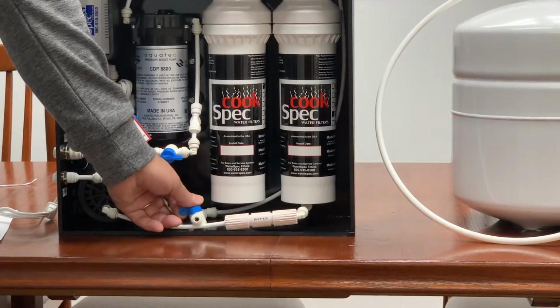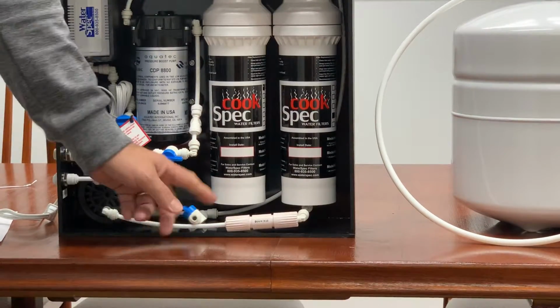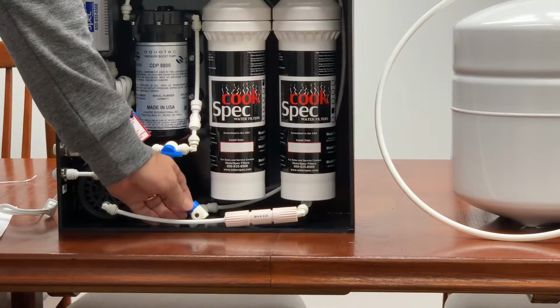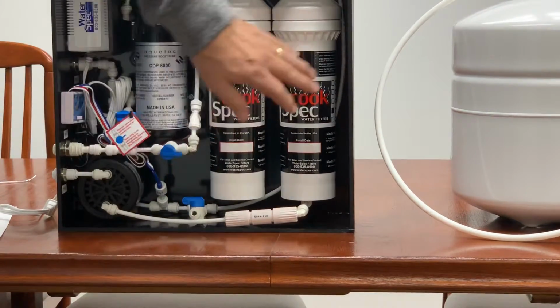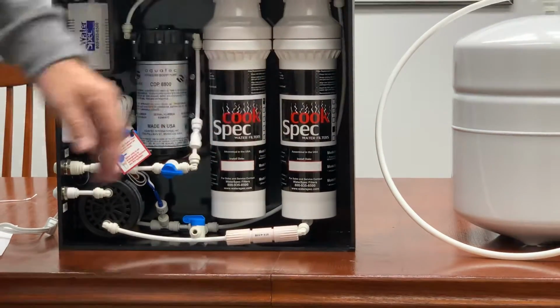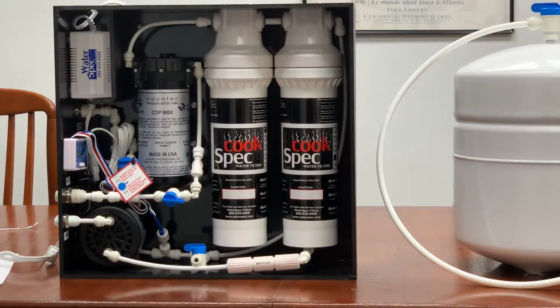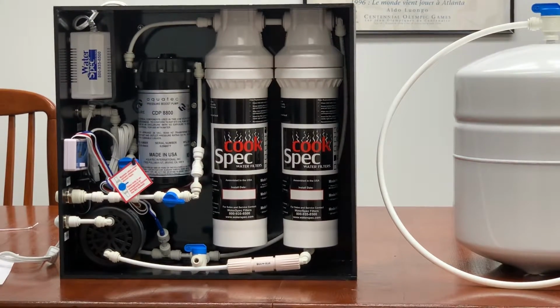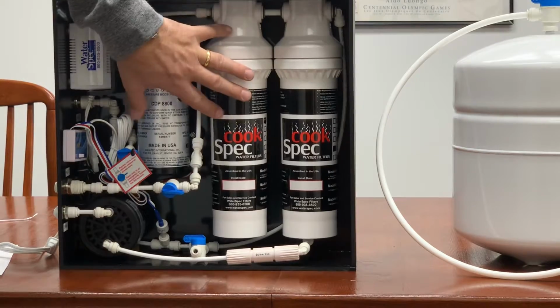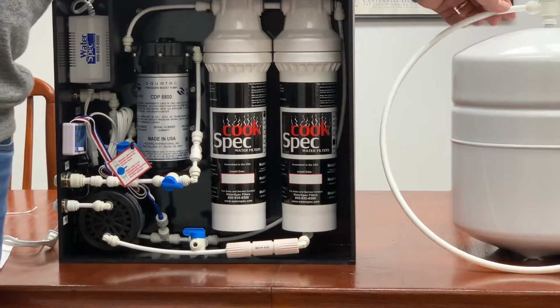Lastly, you have a valve down here which is nothing but a pressure relief valve. It's basically the valve that goes to nowhere. It just opens up and releases pressure so you can change cartridges on the system without any pressure on it. So that covers the general operation of the RO. We'll talk a little bit about the storage tank.